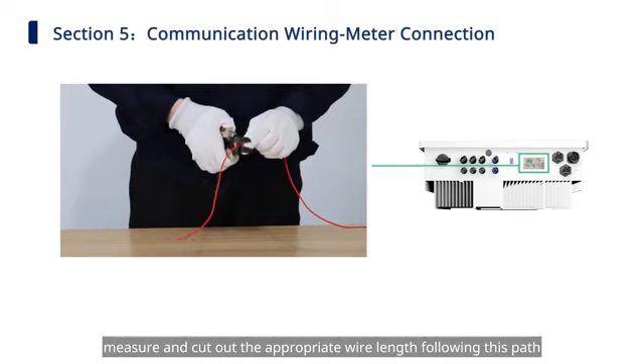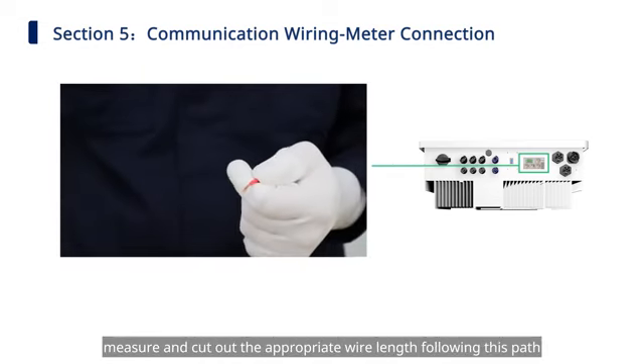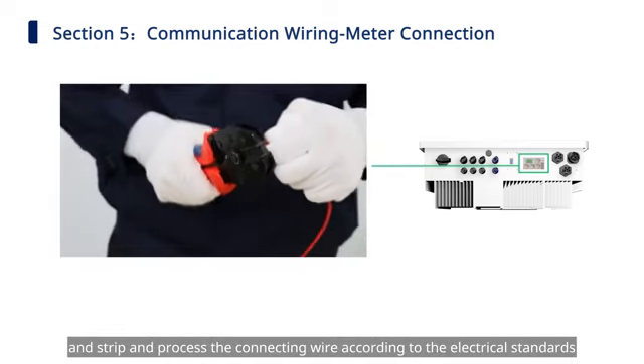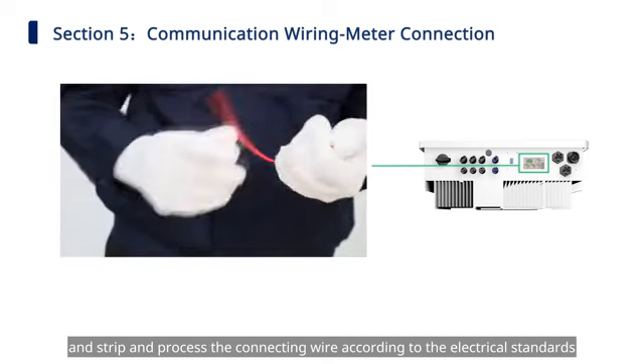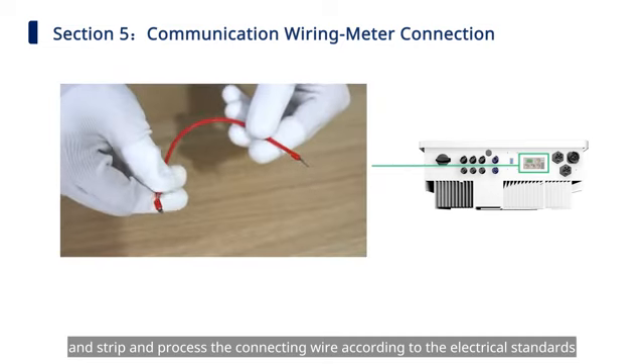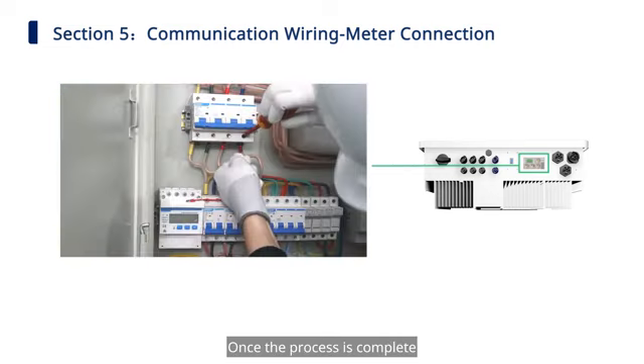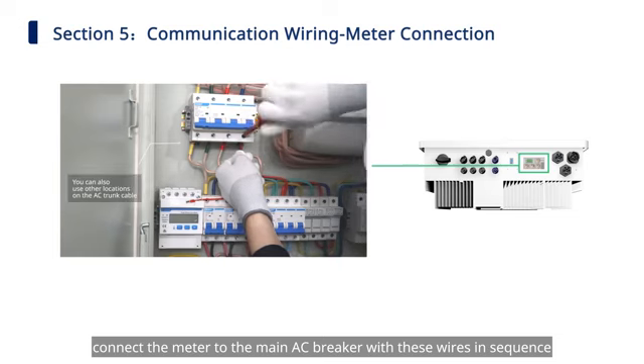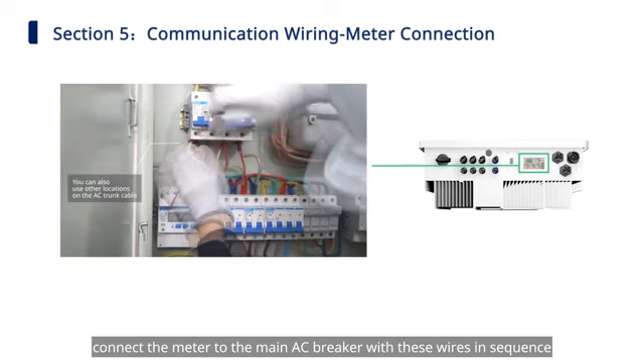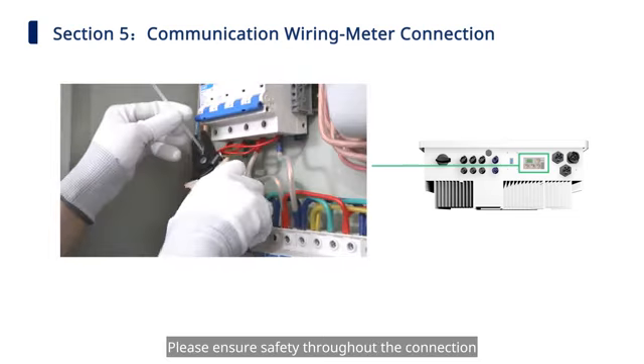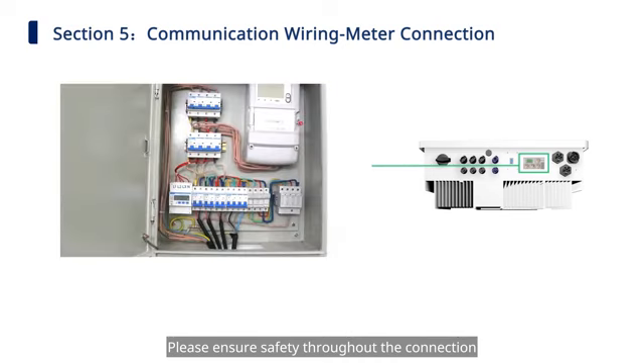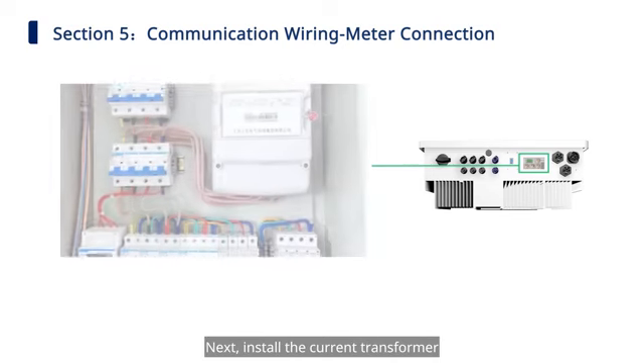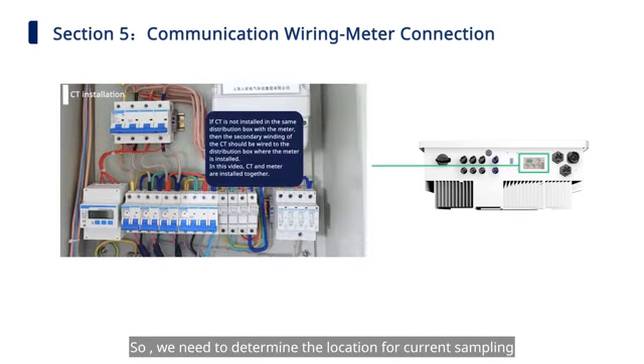Then, measure and cut out the appropriate wire length following this path, and strip and process the connecting wire according to the electrical standards. Once the process is complete, connect the meter to the main AC breaker with these wires in sequence. Please ensure safety throughout the connection. Next, install the current transformer. So we need to determine the location for current sampling.